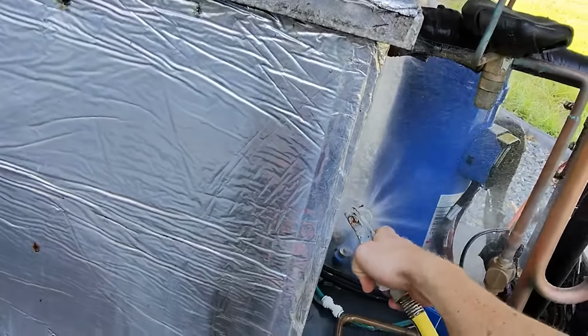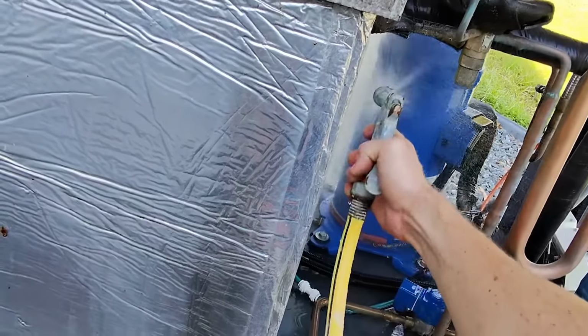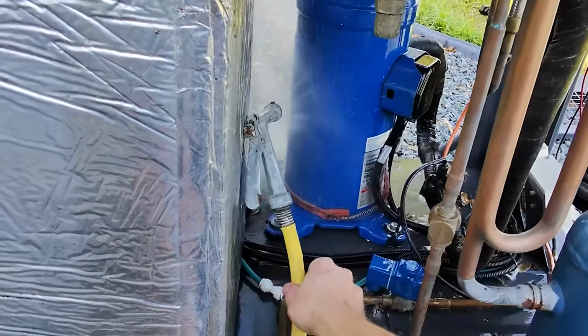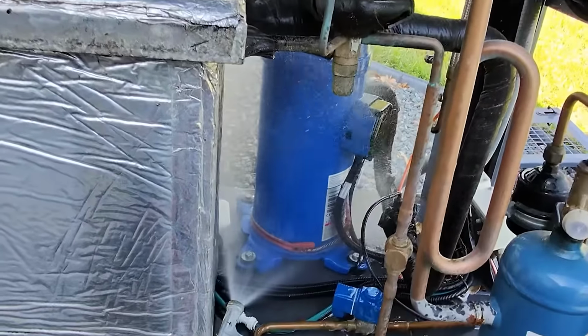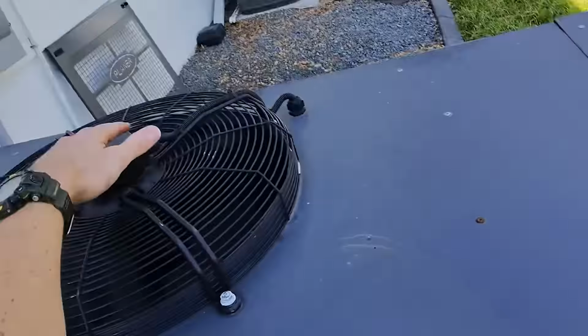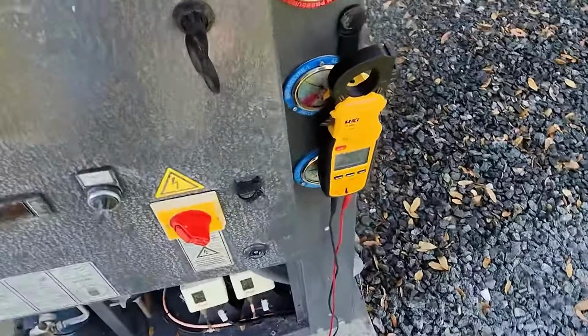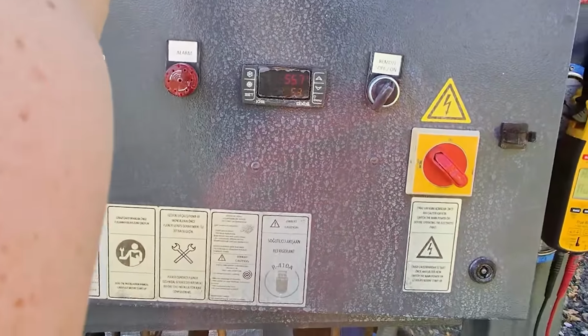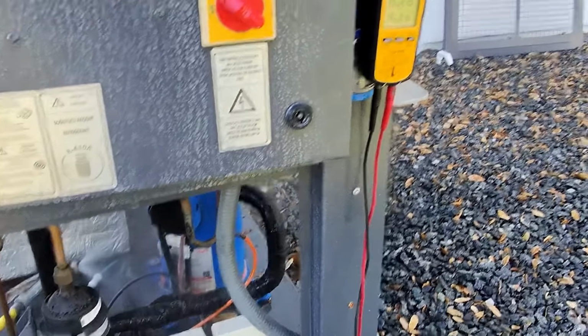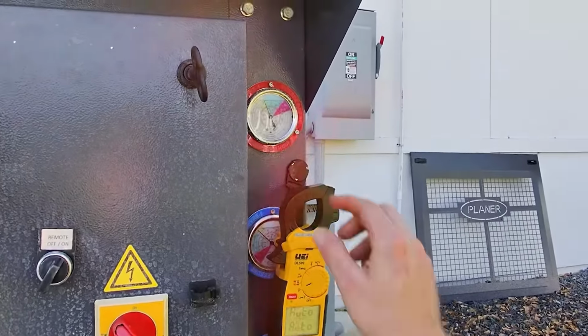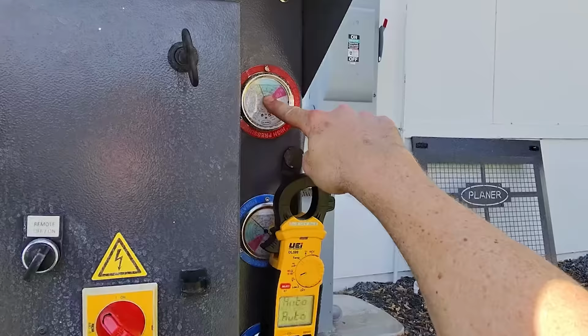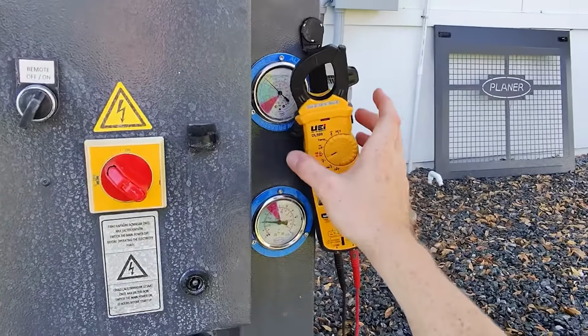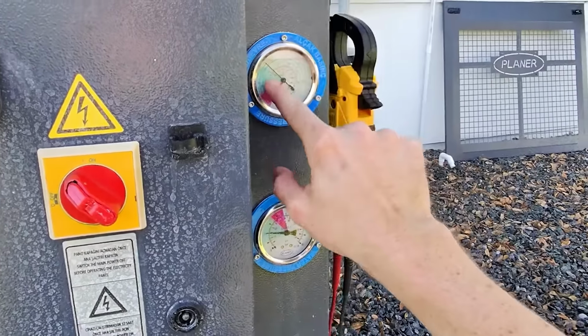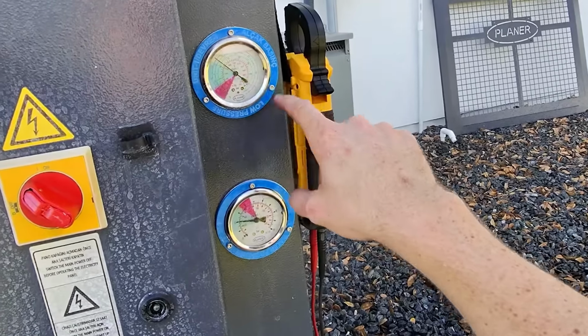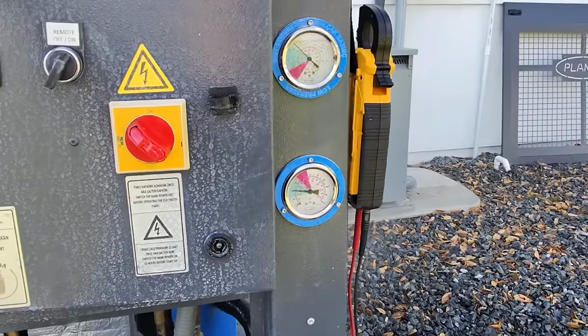Now, I don't ideally want to recommend spraying water in a high voltage unit, but, you know, extenuating circumstances and all. We want this thing fixed, right? We do what we can with what we have, maintaining about a 350 head pressure on this system. So suction pressure is about 170, 175, which is actually pretty high. I mean, it's hot.